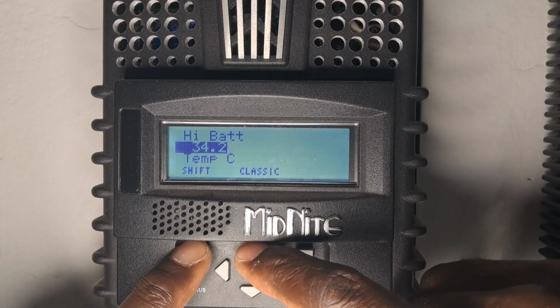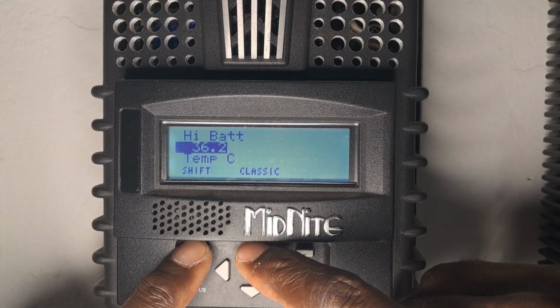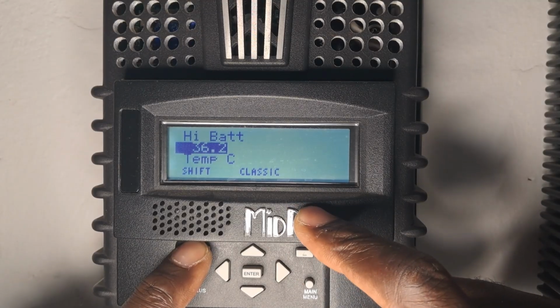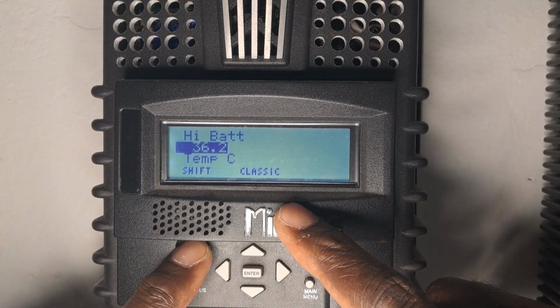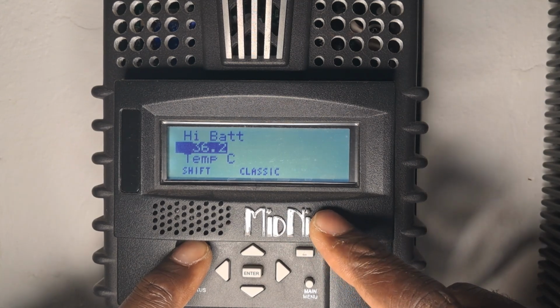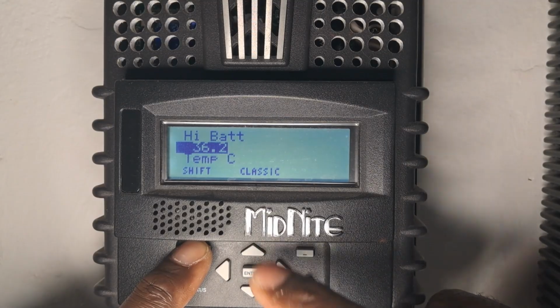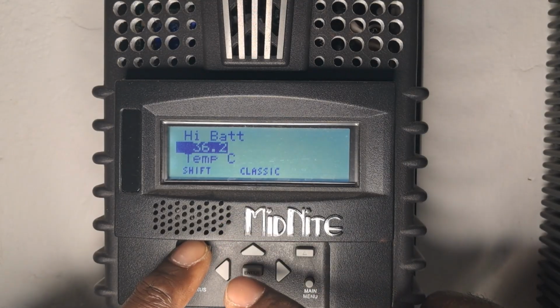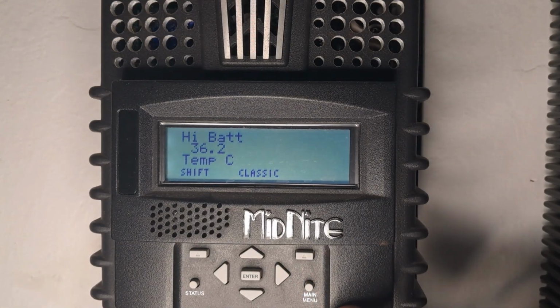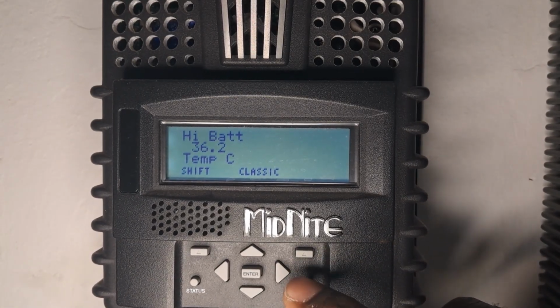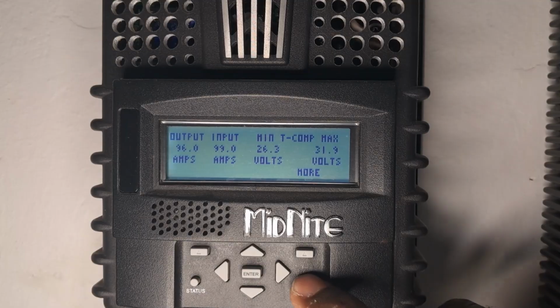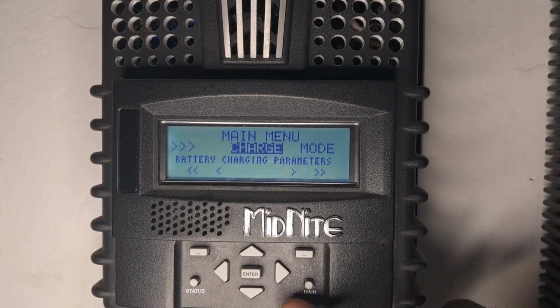So what I'm going to do is set a battery temperature lower than the temperature coming from my temperature sensor, which will shut off the charge controller so no more power goes to the battery. I'll do that by lowering the temperature, currently at 36. I'll enter that, then go back to the main menu to check the temperature coming from the battery.